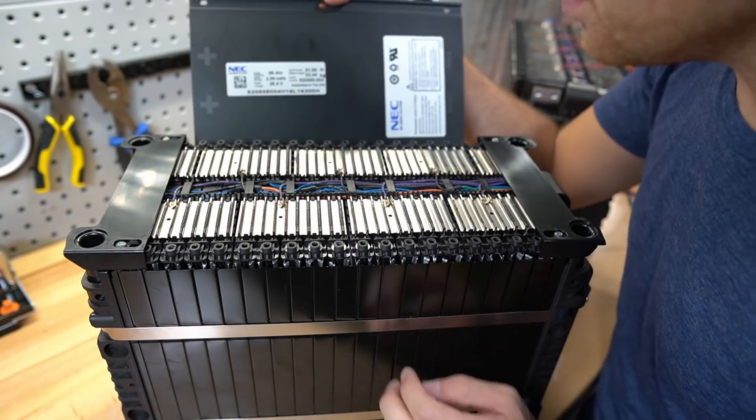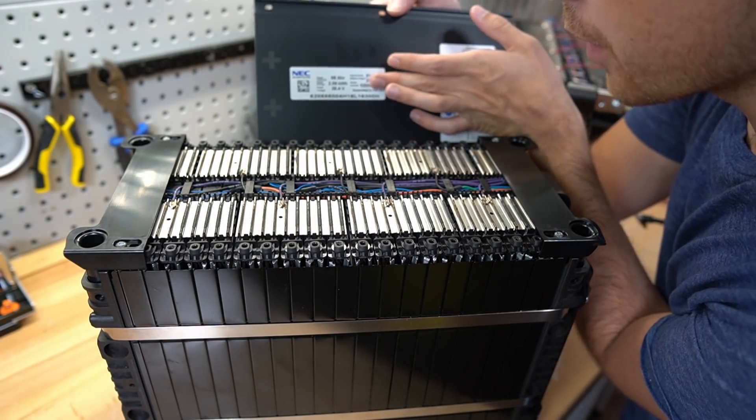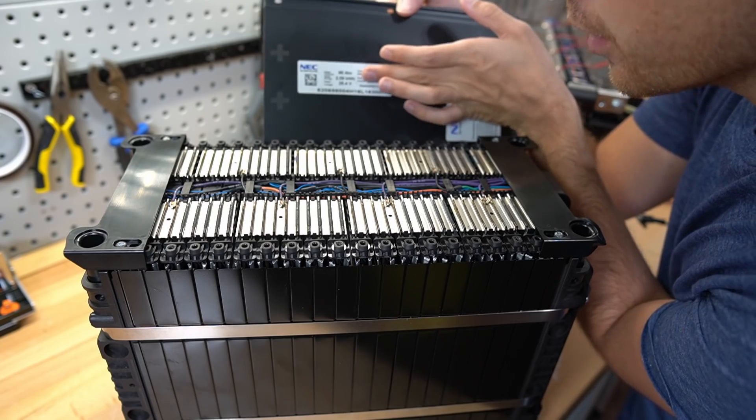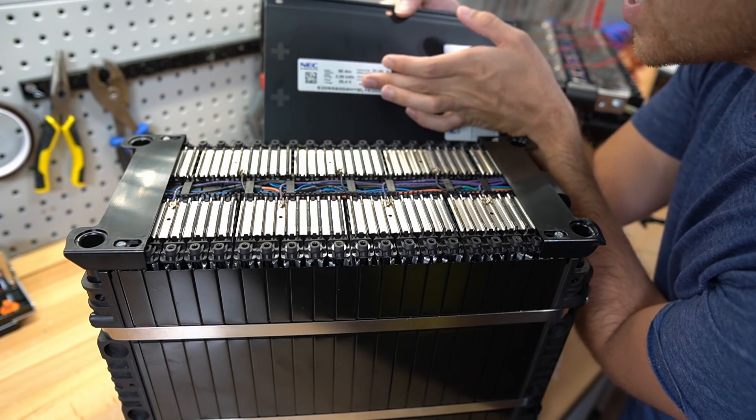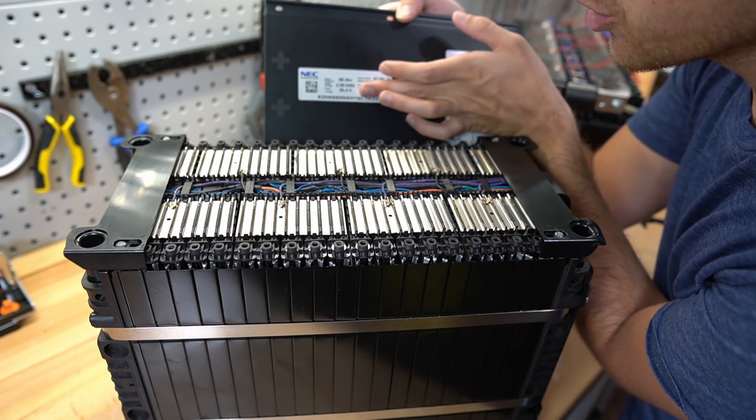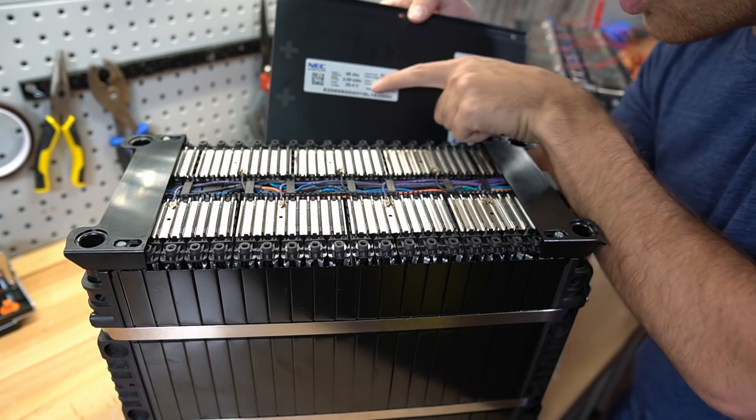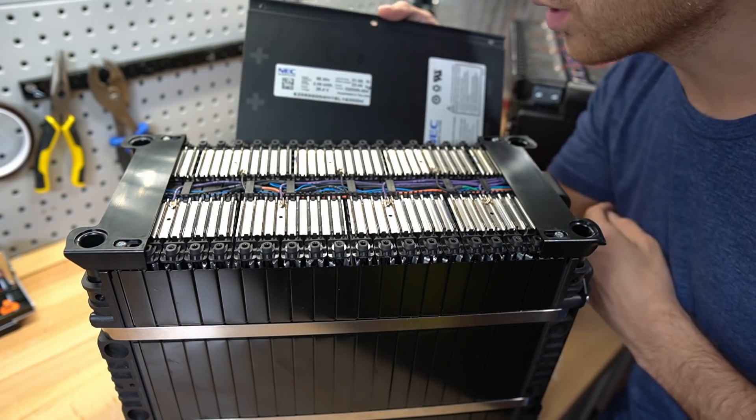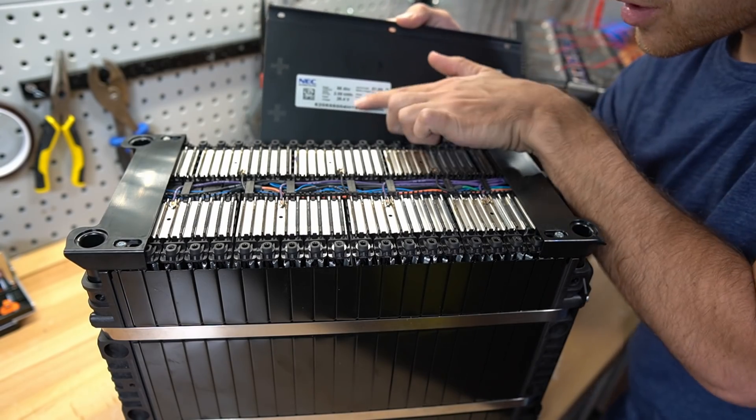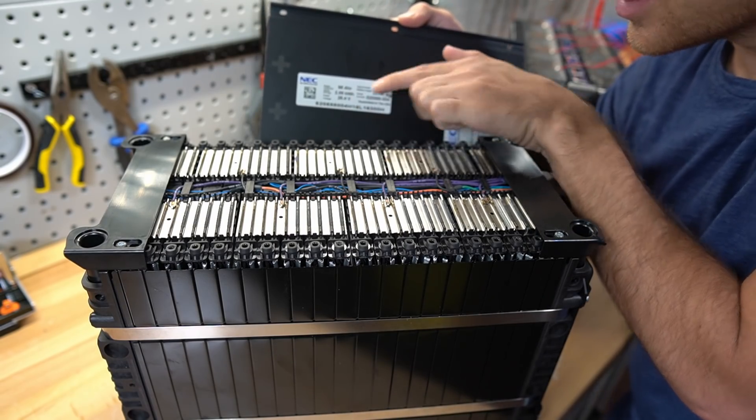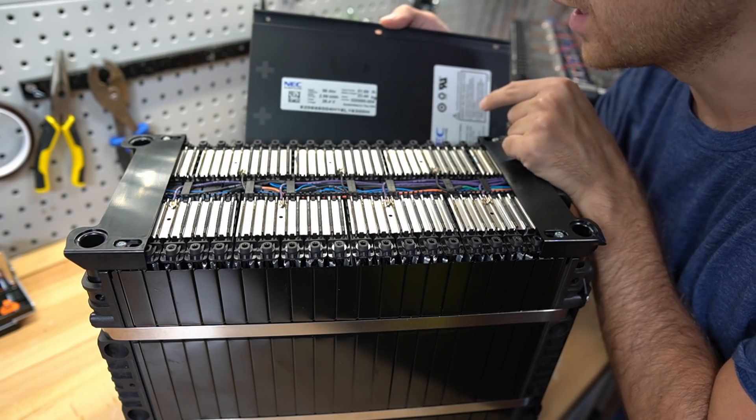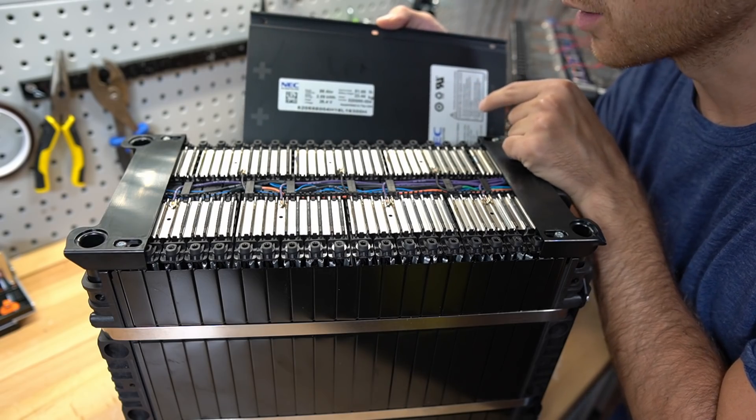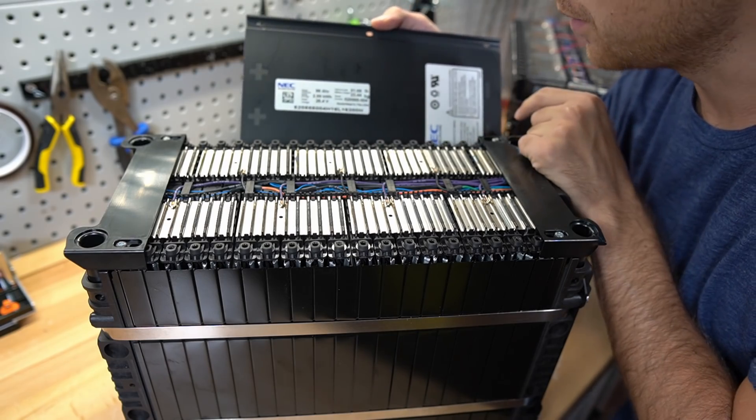On the label, it shows that it's a 98 amp hour battery, 2.59 kilowatt hours, and the rated voltage is 26.4, but this will work with 24 volt equipment. This is just the nominal voltage, and lithium iron phosphate runs a little bit high compared to other chemistries for 24 volt nominal.